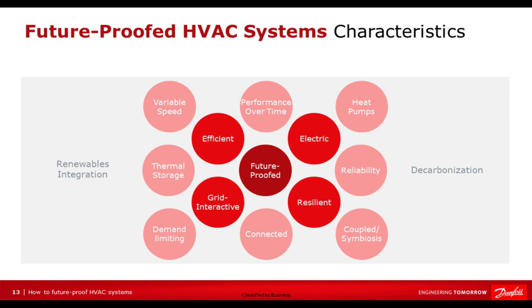And the major factor for HVAC systems related to that is the trend to heat pumps, both air-to-water heat pumps and water-to-water heat pumps. In the past, resiliency was really defined as reliability, especially for mission-critical type systems. What has become much more critical recently is the coupling of those systems and their symbiosis, basically moving heat from where it's not needed to where it is needed, and the tying in of HVAC systems across buildings for more of a microthermal grid, in addition to the microgrid trend you see from the power side.